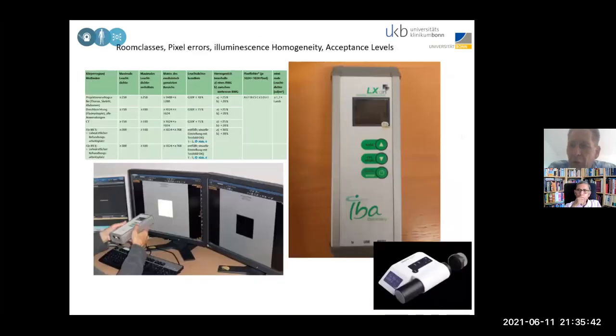So how do you do that? How do you do monitor controlling? You see in the lower left corner somebody sitting in front of one of those monitors, having the device on the right-hand side and putting that at a certain distance. The distance is to be described, at least 10 centimeters. It could be more, it could be less. You have to be sure that you face the device on the square in the middle of the image. And you have to be sure that the background luminosity of your room, so your room class, is accepted. Otherwise, the homogeneity is not accepted.